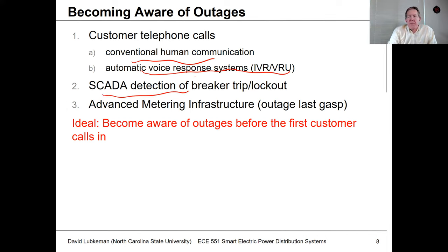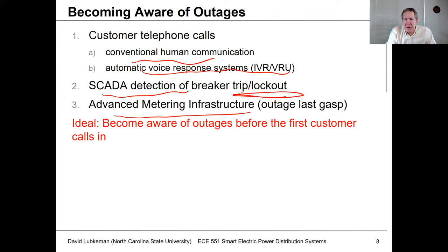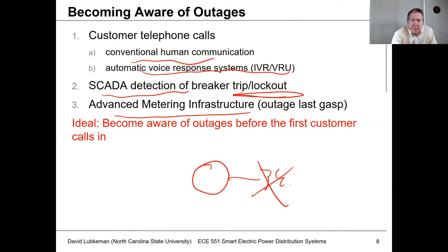You'll also have data through your SCADA when a breaker operates, because the relay sends an event message to SCADA saying something happened and the circuit breaker opened. You're mostly interested in knowing whether you get a lockout. Nowadays a lot of this is driven through advanced metering infrastructure — what we call the outage last gasp. When a meter loses power, it has stored energy in a capacitor, enough to send one last message saying it's lost power. Most residential meters don't have batteries, so they rely on that stored capacitor energy.